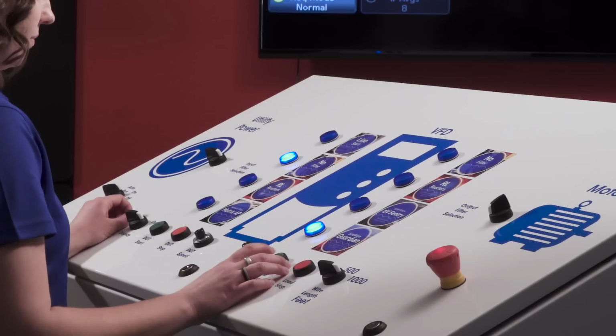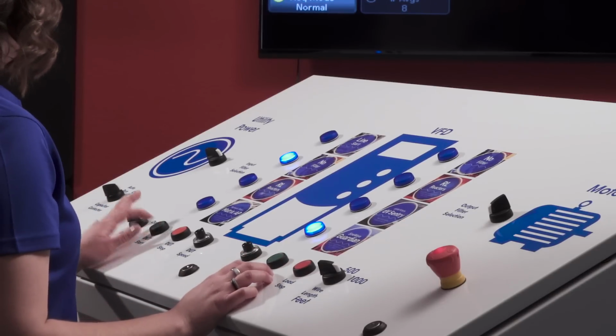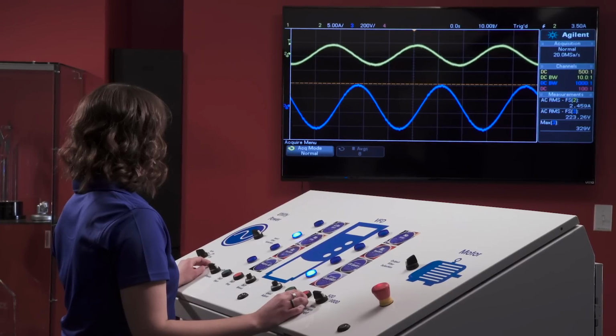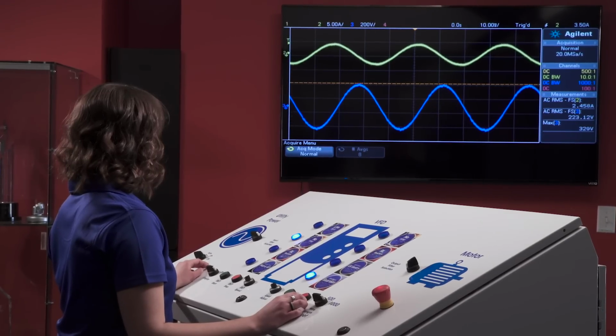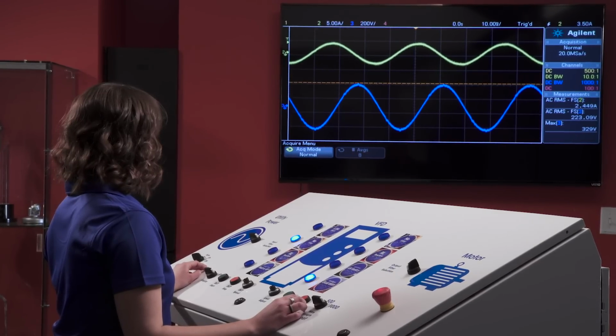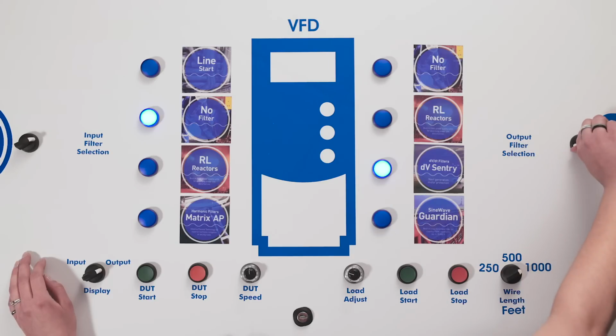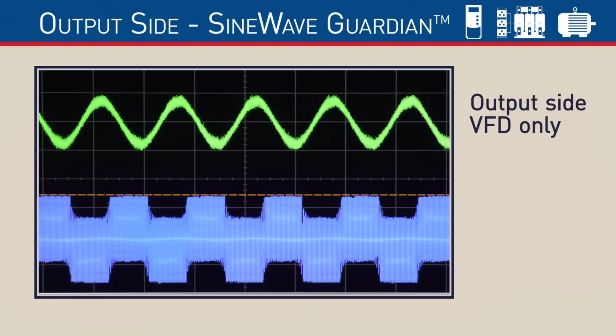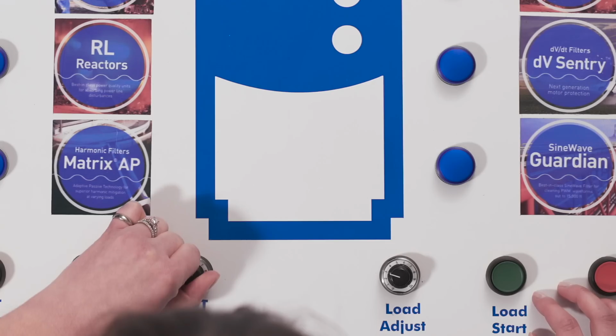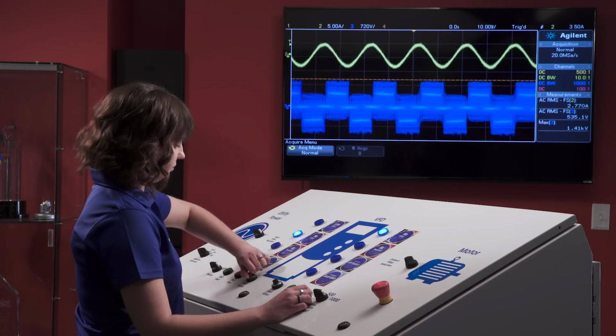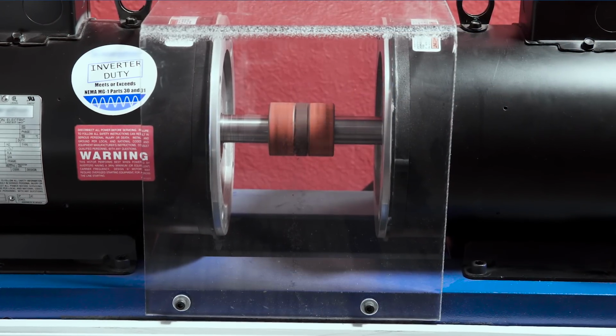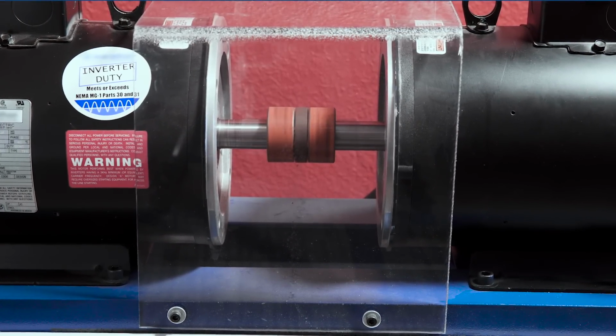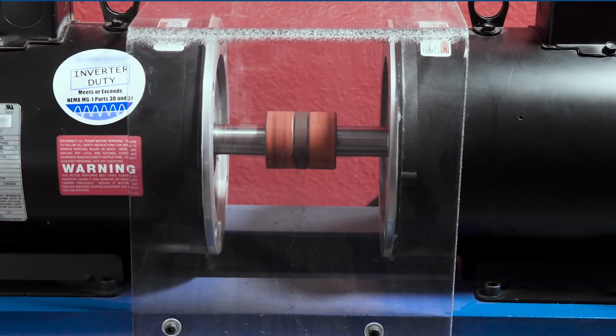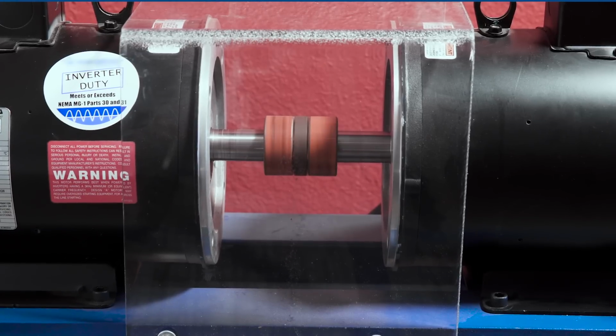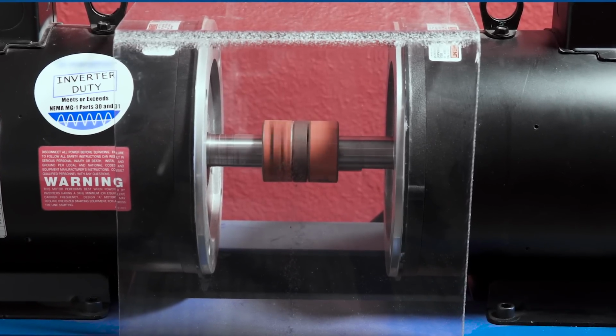With the Sine Wave Guardian now enabled, we can see it has taken the output PWM signal and turned it into a nice-looking sine wave. But wait, there's more! Let's run the system again with no filter. Do you hear that loud screeching noise coming from the motor? As we increase the speed, we can hear it intensify. In critical applications, such as an HVAC system where noise might become an issue, adding the Sine Wave Guardian filter goes a long way in making the system run quieter.